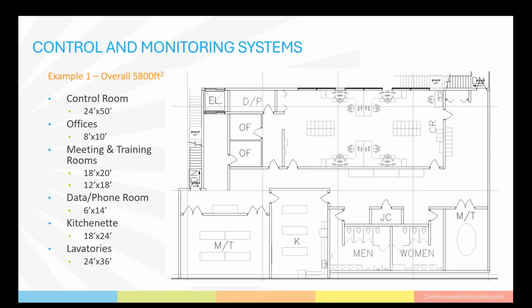Example one is a 5,800 square feet control room, which is fairly large to accommodate multiple DCS style monitoring systems with 4 operator stations, as well as cabinets for storage of procedures and operating manuals. Also, most control rooms will have hard copies of P&IDs and control diagrams. So there's also lay down space to review any of the on-hand documentation. This client had specific needs for training and meeting rooms, as well as offices, a kitchenette, and lavatories. This one is on the 2nd floor, so it required room for an elevator and 2 sets of stairs for egress.